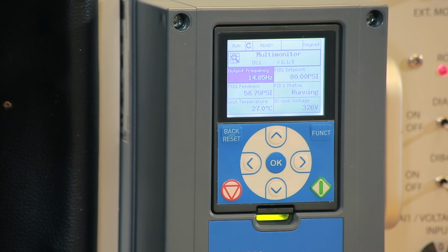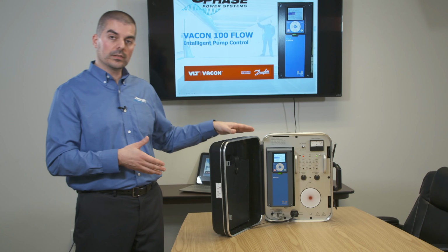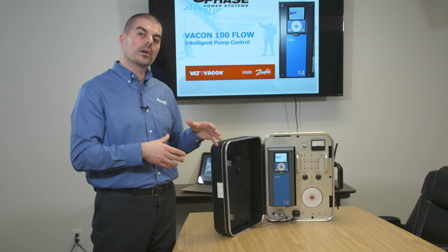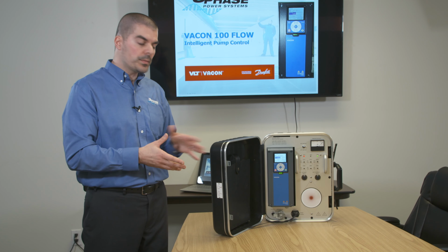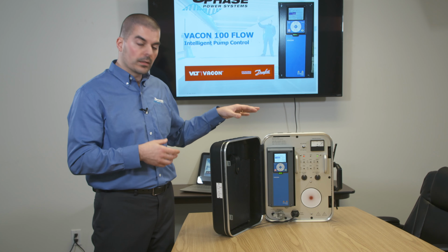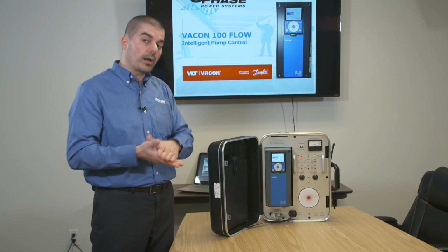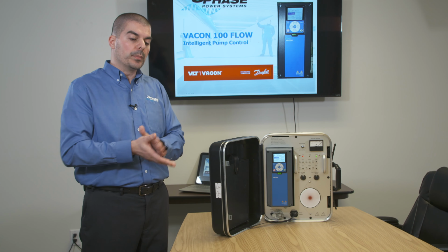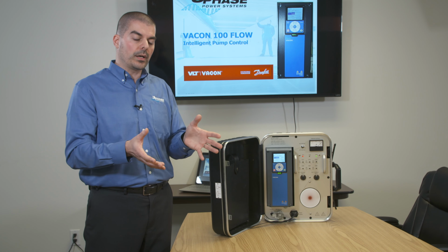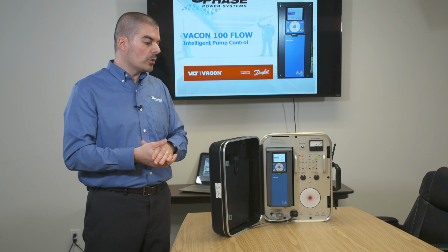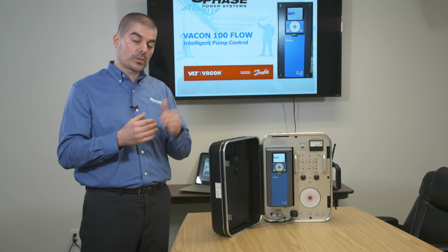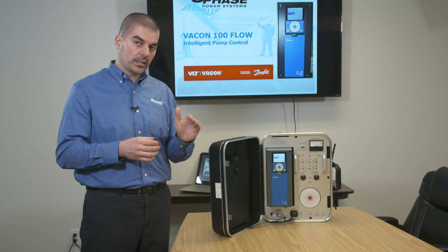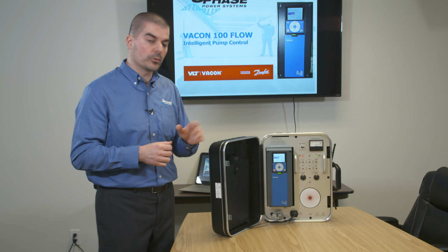So we saw how the drive runs. Now we're going to stop it and program soft fill. What this means is that the PID controller right now ramped up to 60 hertz immediately, but we don't want the water pipes to have water hammer. So we're going to program the drive to do a soft fill of the pipes gently to eliminate water hammer, and we'll show how to do that.